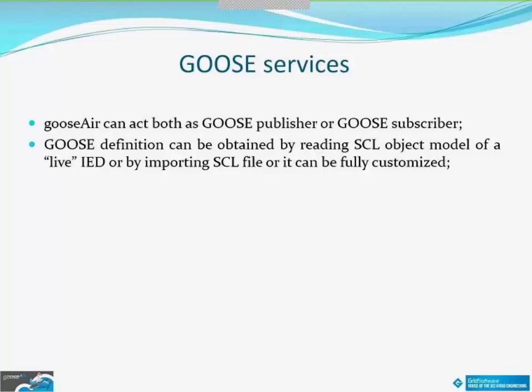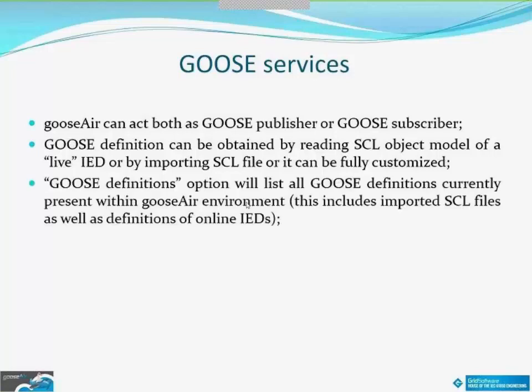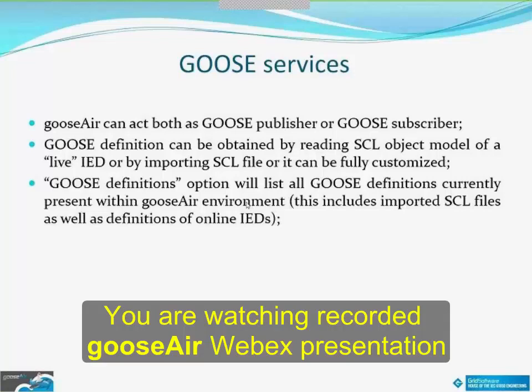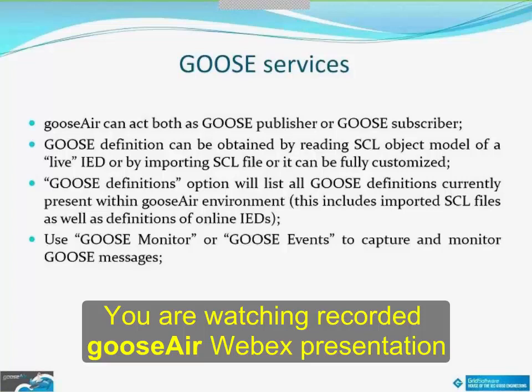Goose messages could also be fully customized, which means that no import or reading of goose definitions is required whatsoever. Therefore, parameters of the goose control block as well as dataset members are all up to the user to define. Now, when working with multiple IEDs, I recommend using the goose definition option, which will allocate and present all goose definitions which are available for the user to simulate. This also includes goose configurations obtained from a live IED or from an imported SCL file. Monitoring of goose traffic is available in two different ways, using the goose monitor tool and the goose event monitor tool.